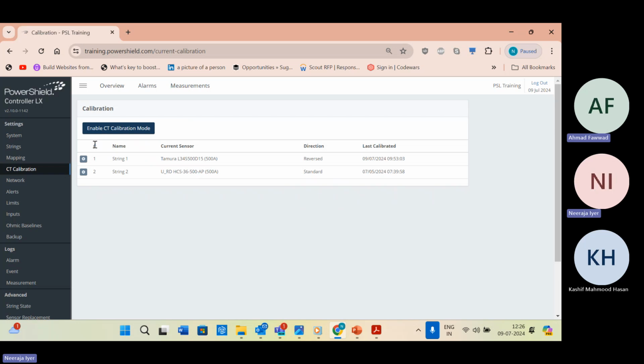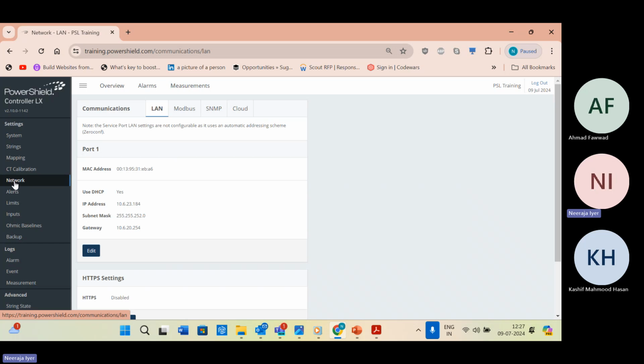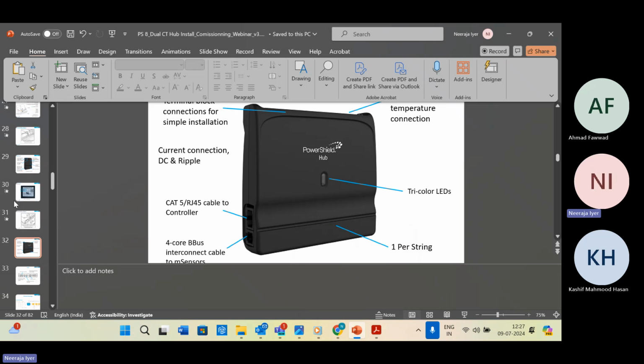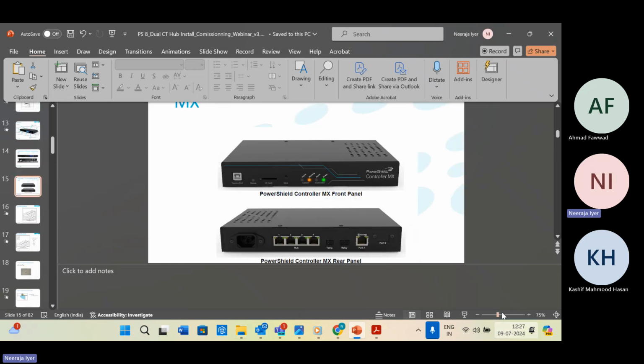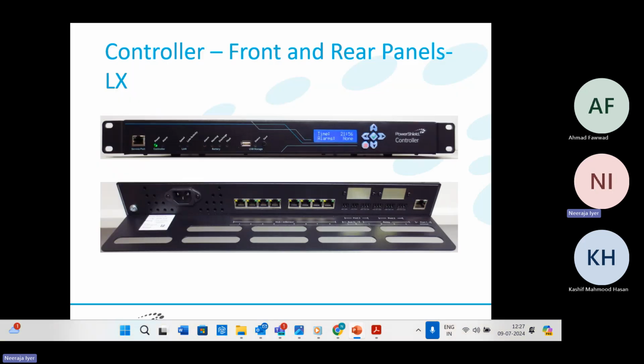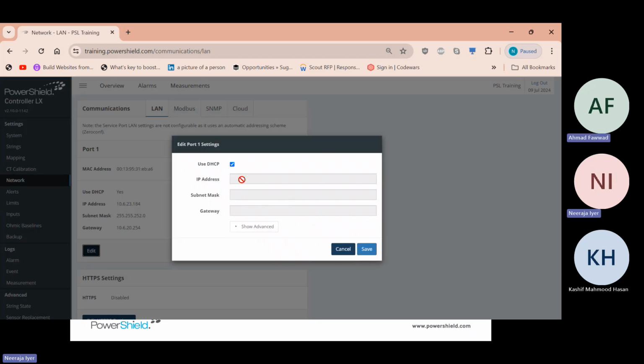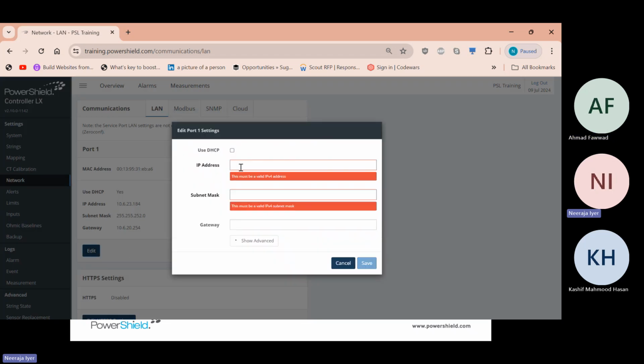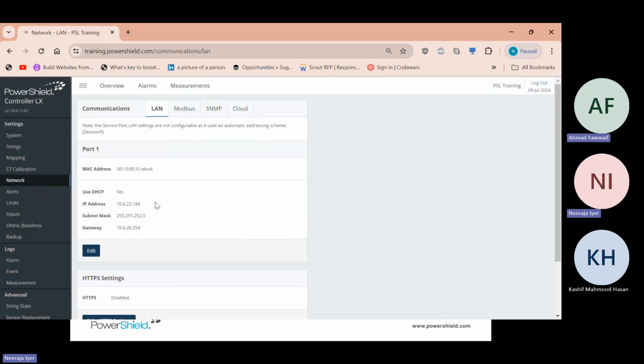Any questions? Yes. What if we want to integrate the system with the customer's BMS? How can we change the dynamic IP as per the customer requirement? Not a problem. Go to the network section. You can see here port 1, LAN is given. This port 1 is on the rear side of the controller. All you have to do is click edit. Default is DHCP. Just uncheck that, and you can enter whatever IP it is. I can't do this here.